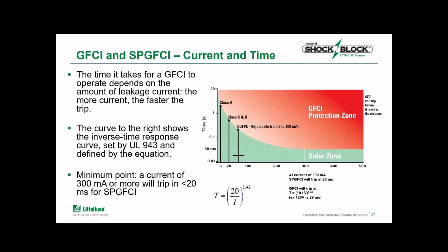So on this slide here, we're showing the inverse time curve that is used as the base for both UL 943 and UL 943C. That 20 milliamp pickup level, you can see designated with class C and D on the curve, is required to operate a little faster than the class A GFCI at that pickup level. So you can just trace the curve there to see the required reaction time at those current levels.